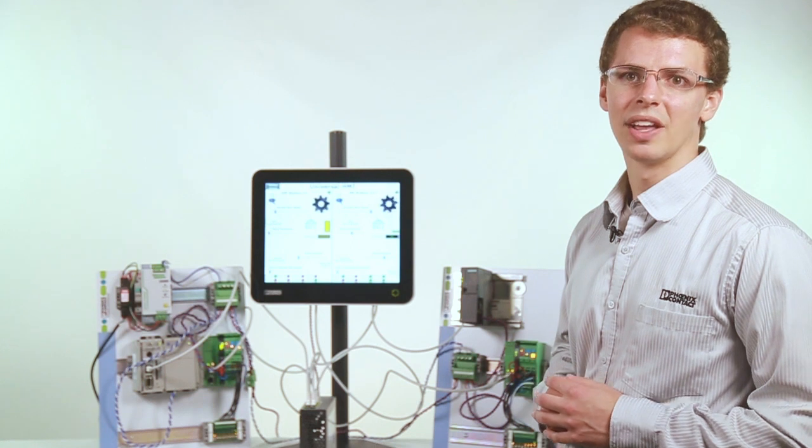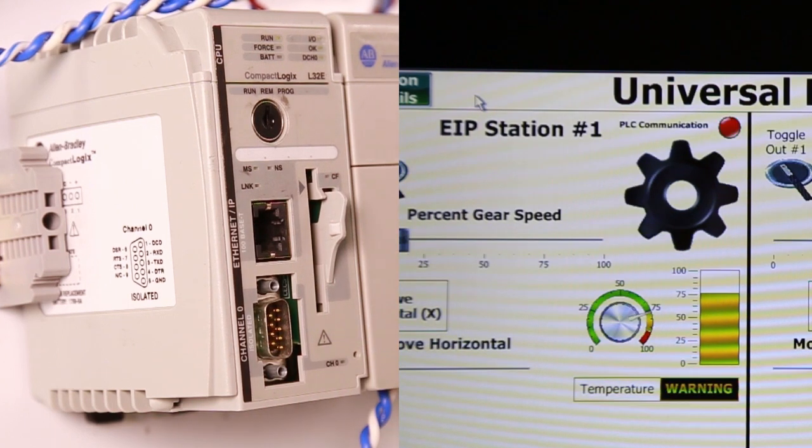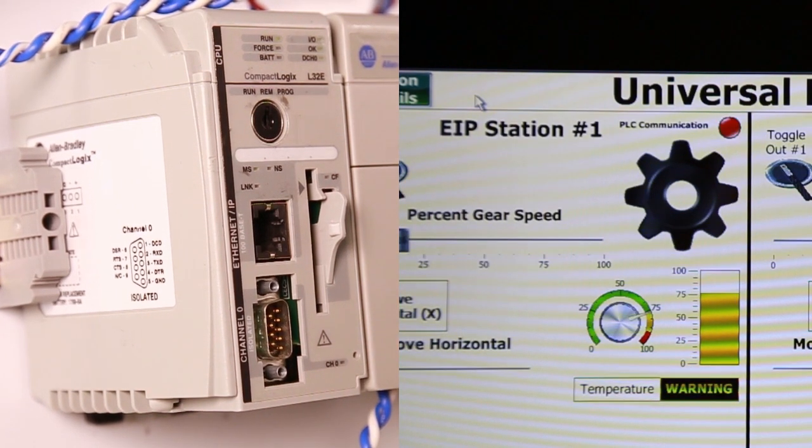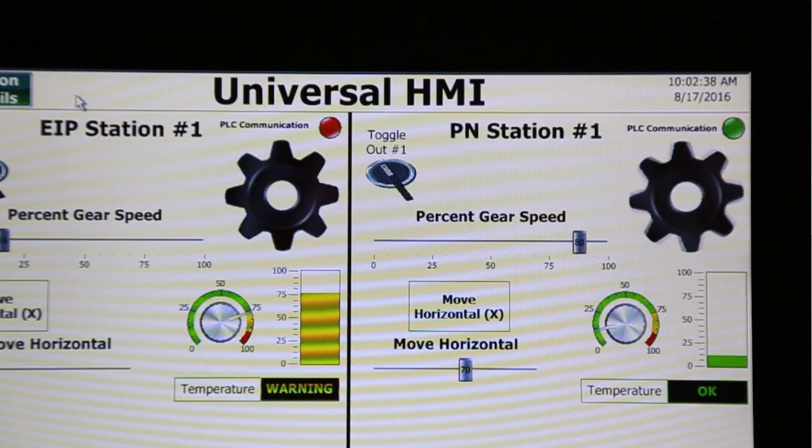On the Ethernet IP side, we'll see the same thing. Phoenix Contact's Universal HMI detects that the Rockwell PLC loses communication and stops updating those values, while the Profinet communication is still up and running.